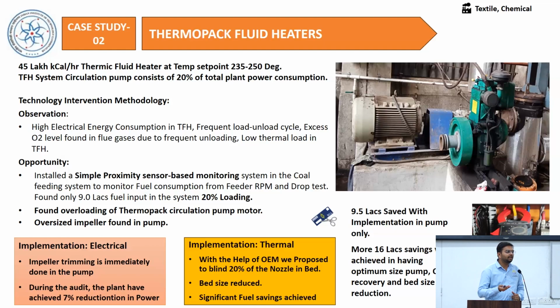Now the pump is at 37 kilowatt as per the motor specification, and we recommend reducing it further with a 30 kilowatt motor, so that they can achieve almost 20 kilowatt savings, which is equivalent to 7% of the total plant load. That is a significant saving they have achieved in this pump, because this system was introduced just 2 months back. So the OEM itself trimmed the impeller and supplied the trimmed impeller to the industry, and the industry is having the savings with this implementation.